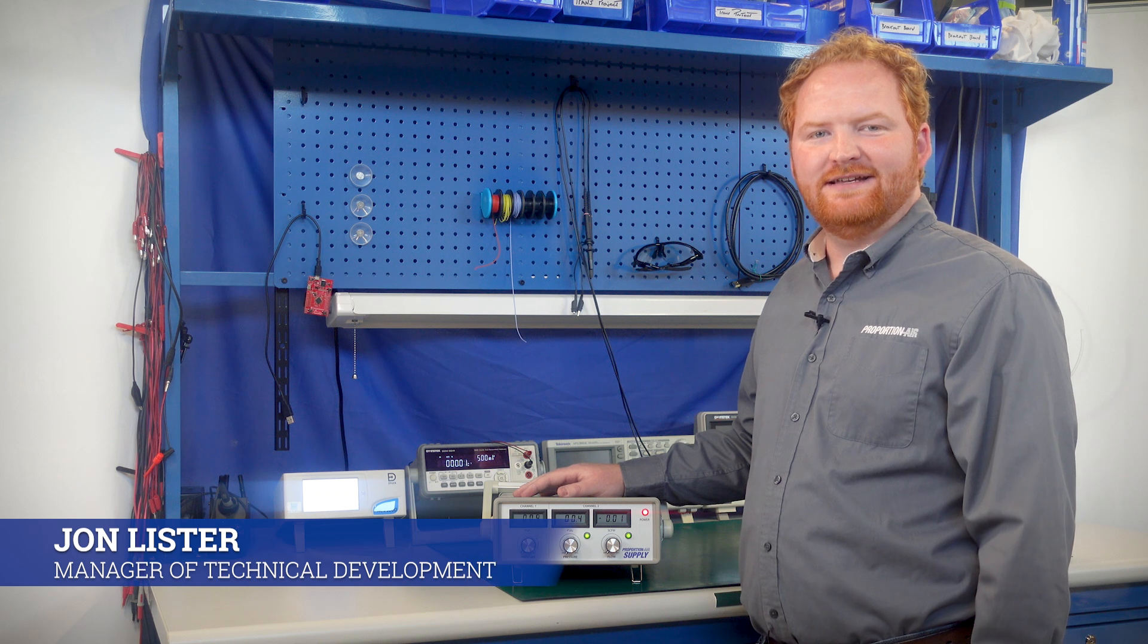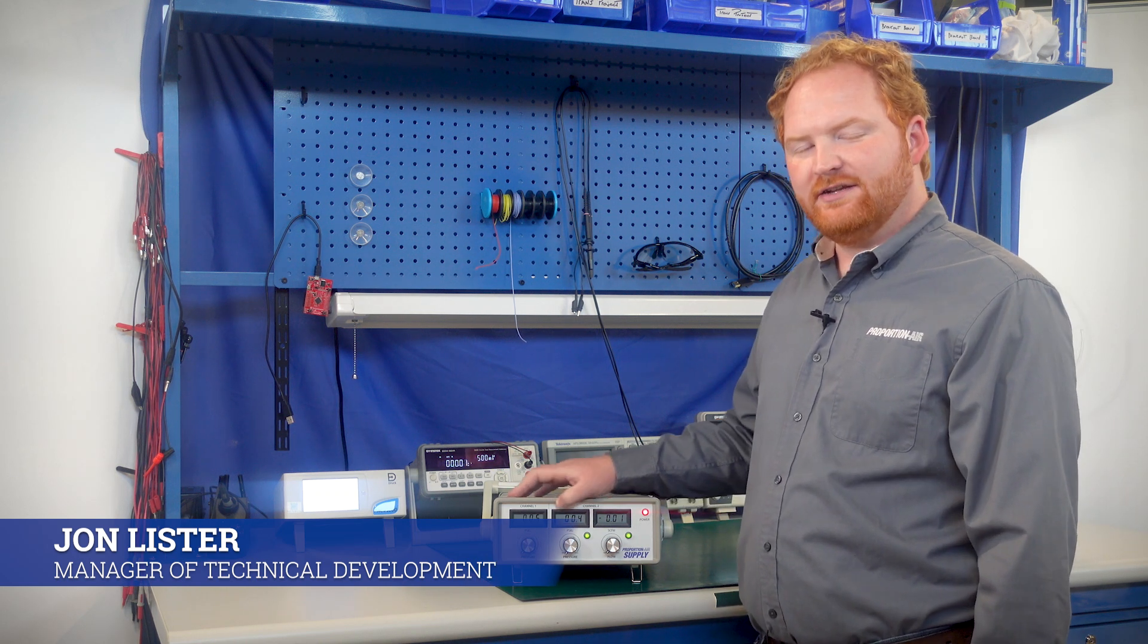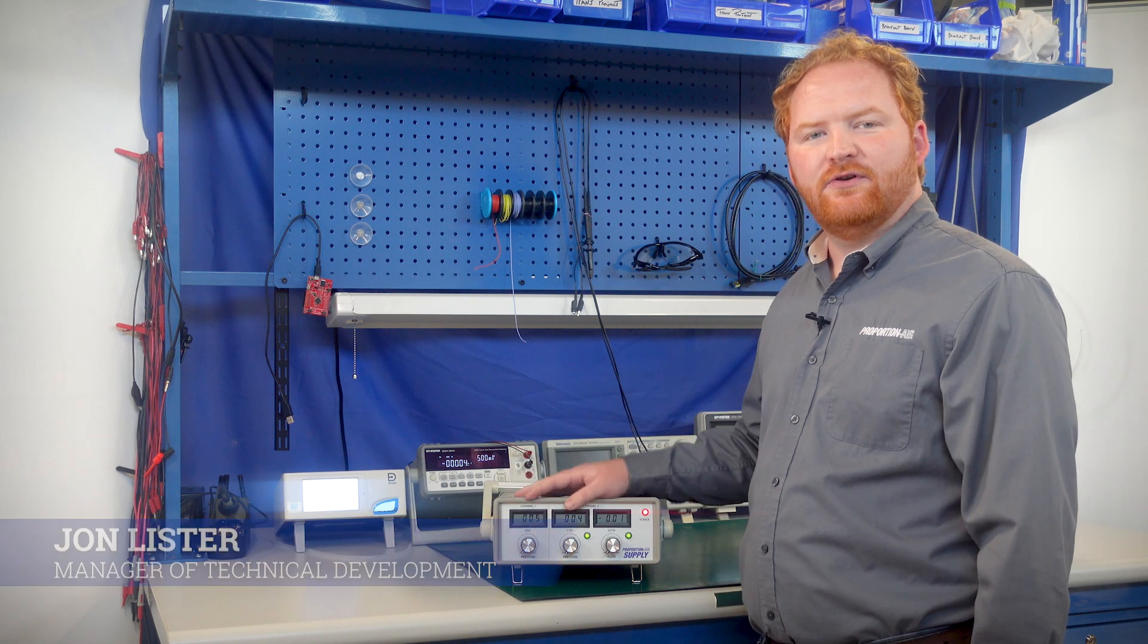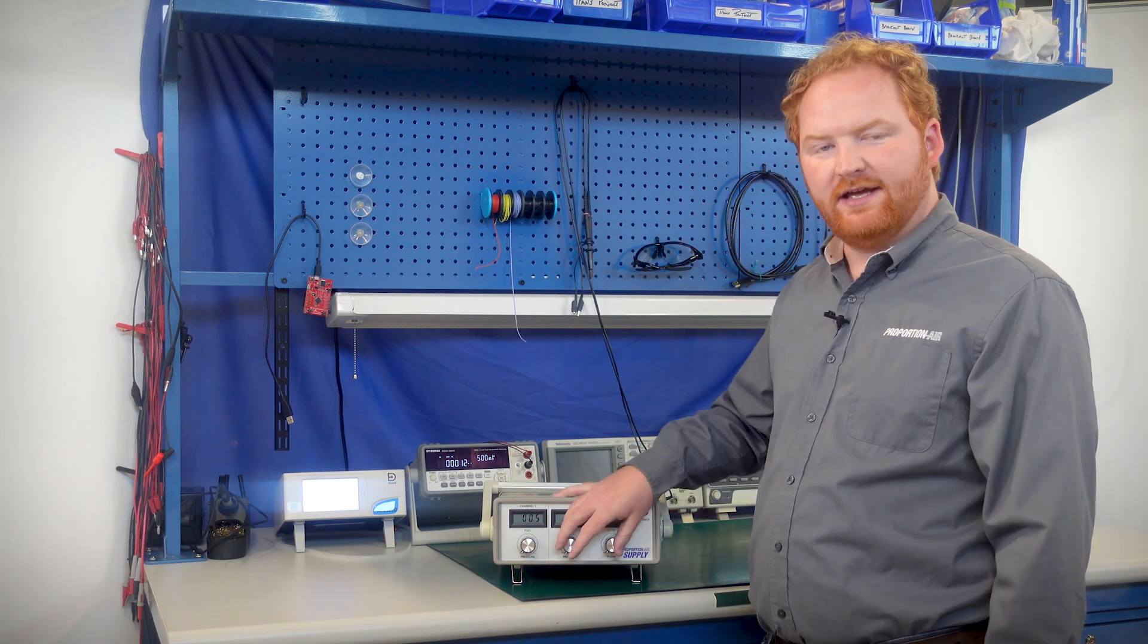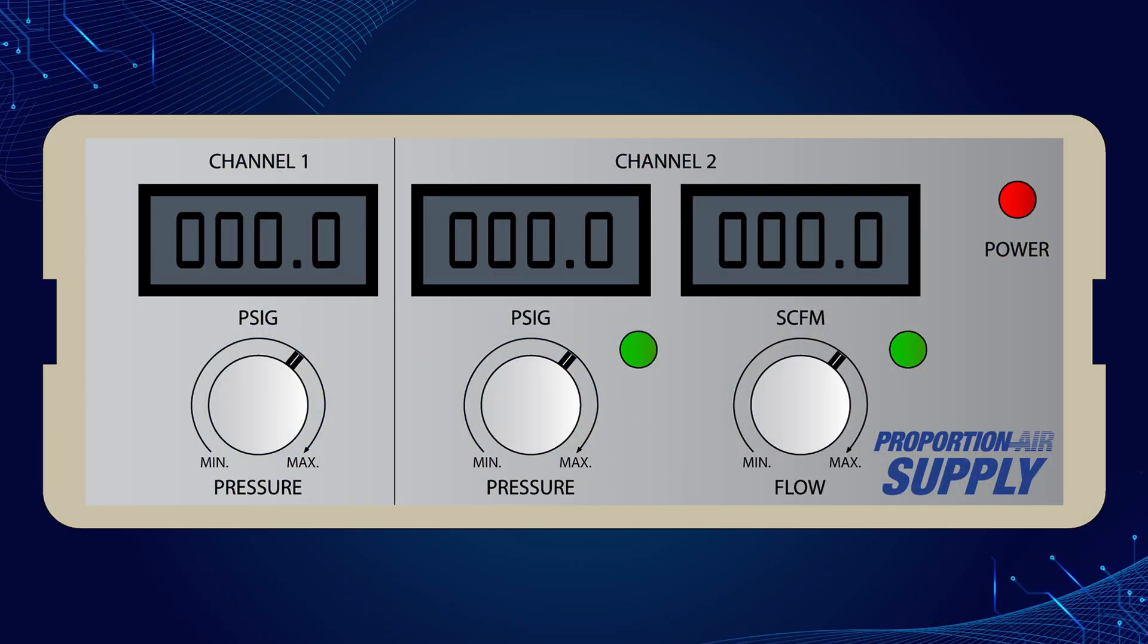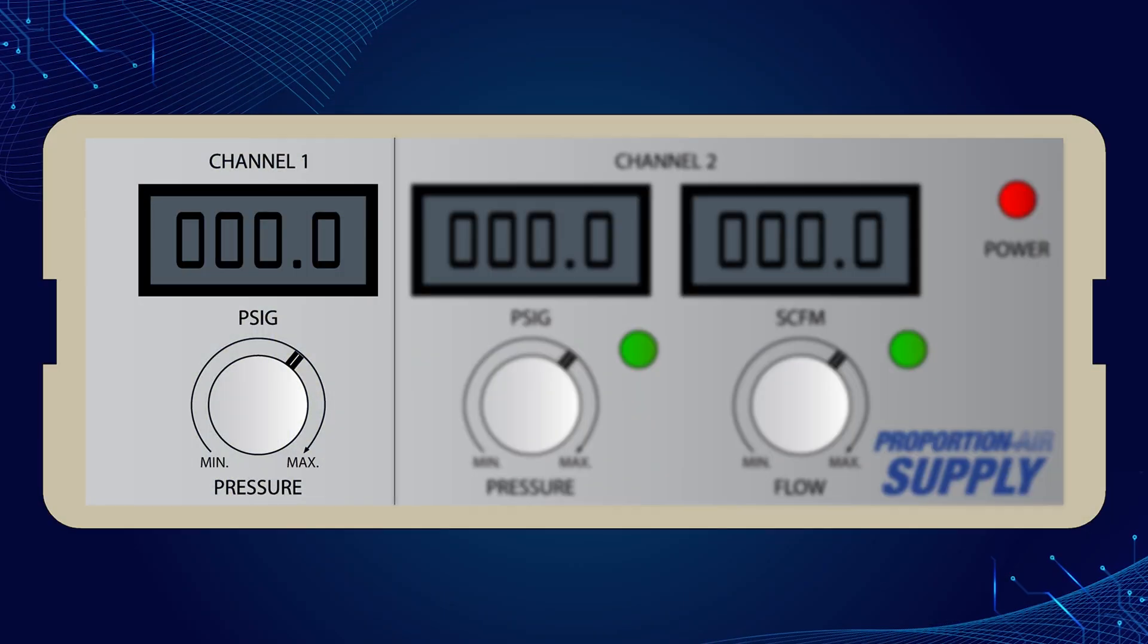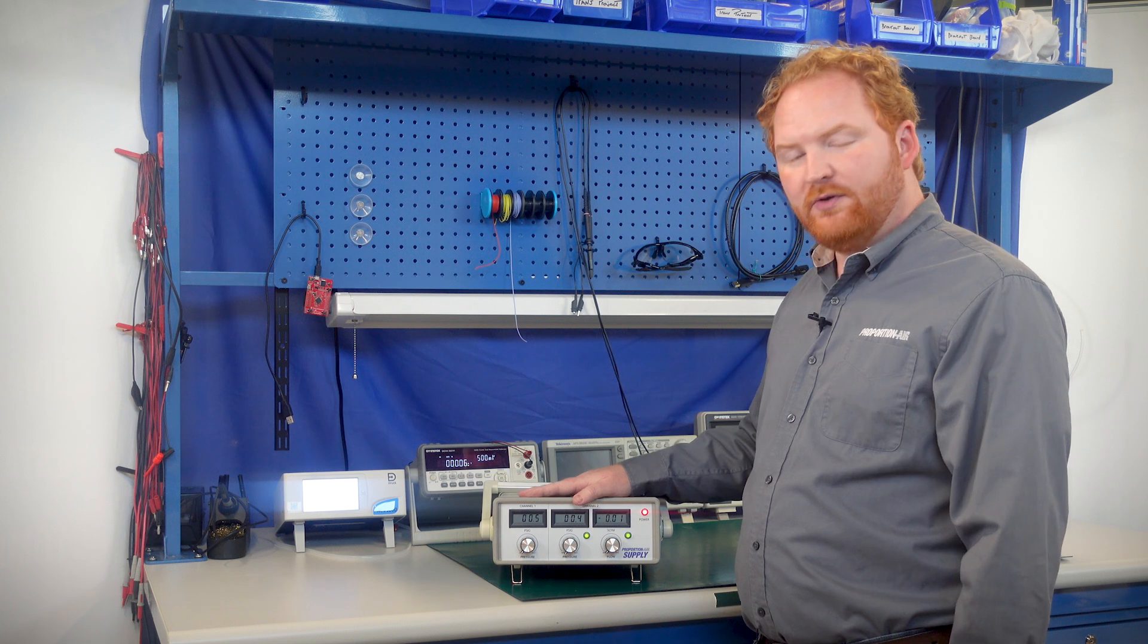The Proportion Air Supply is the pneumatic equivalent of an electronic power supply. On an electronic power supply you control the voltage and the current. On the Proportion Air Supply you control the pressure and the flow. There are two channels: channel one regulates pressure only, and channel two regulates pressure and flow.